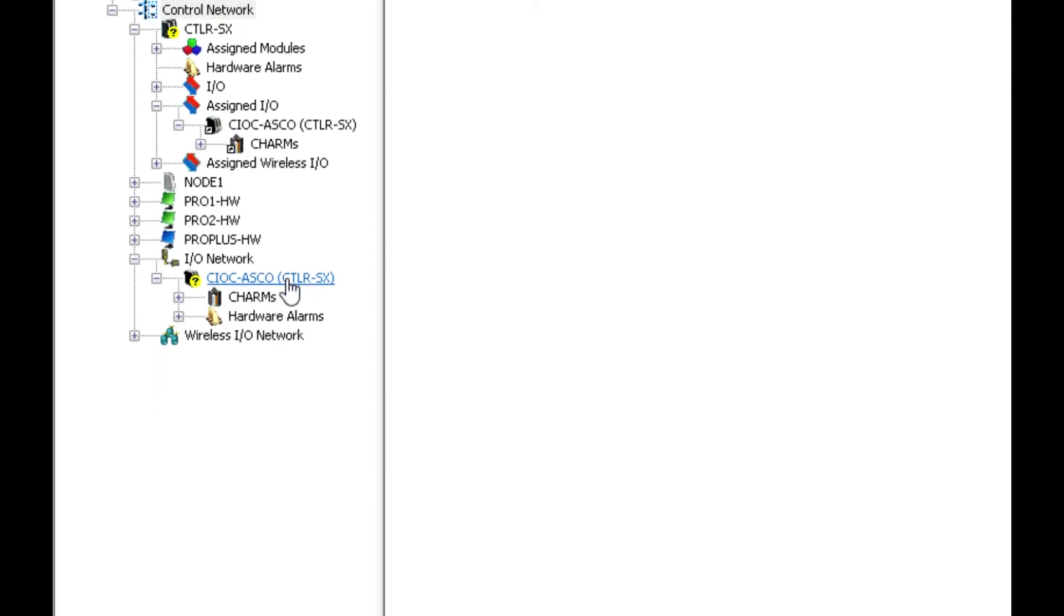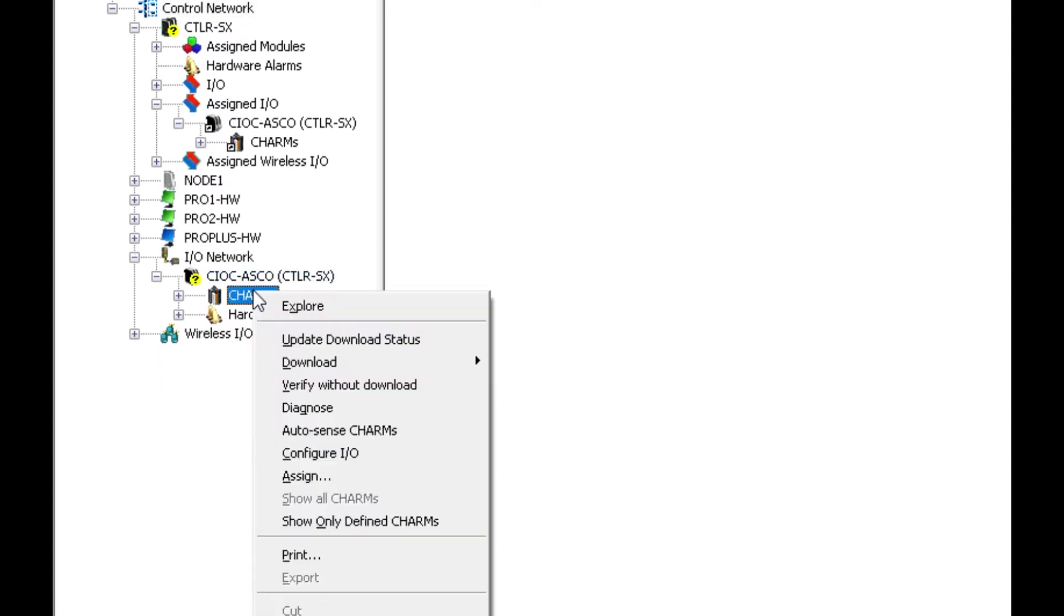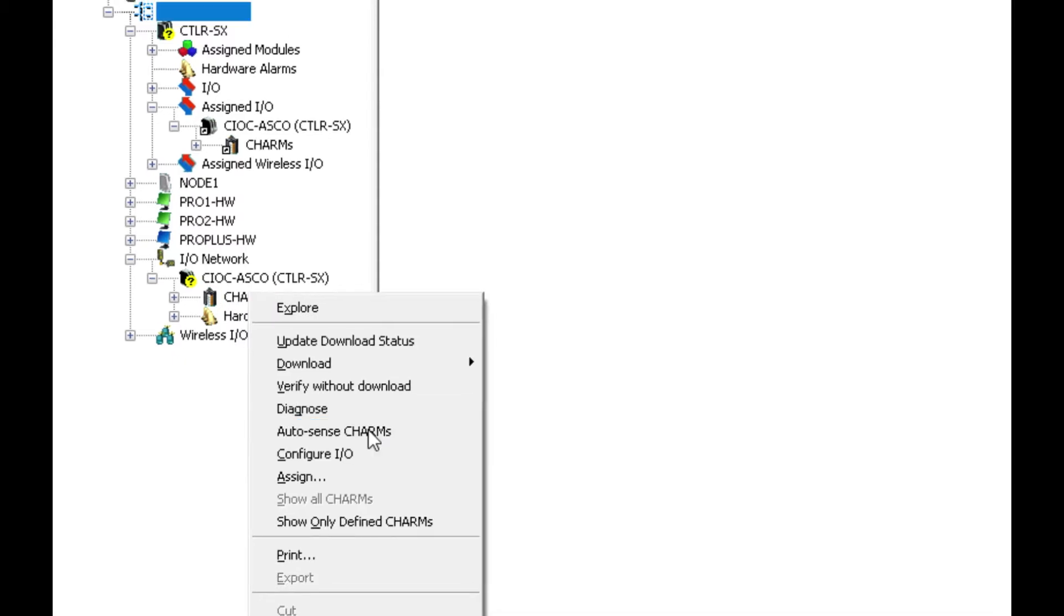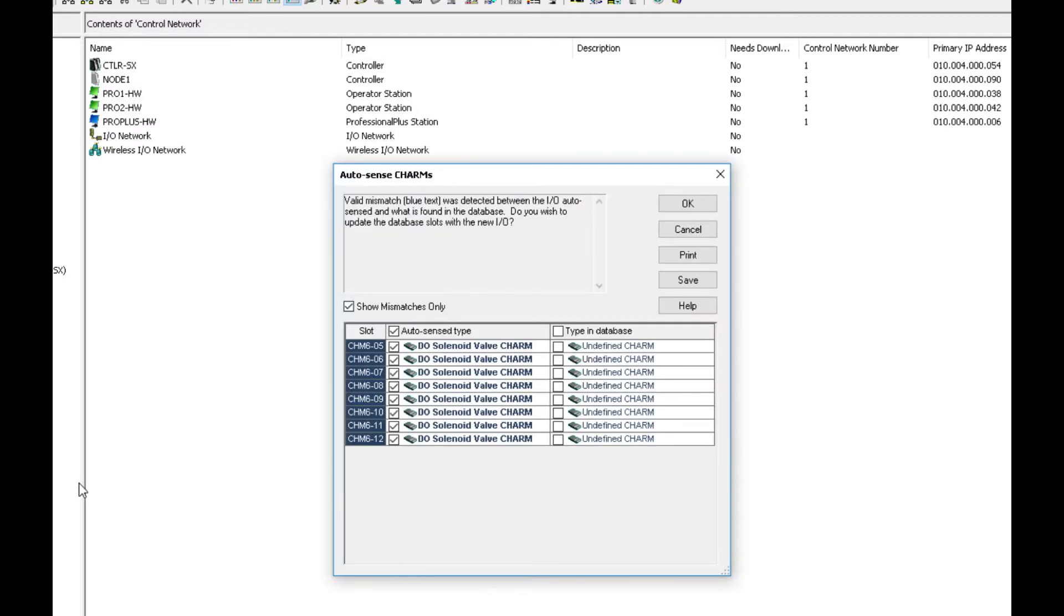And we have the auto sensing functionality in Delta V so I can auto sense charms right in here and it will come up and show you if there's a mismatch or any new charm types in the I.O. structure. And as you can see now it auto sensed a number of new charms and these are the DO solenoid valve charms that are associated with the ASCO 580 charm node.